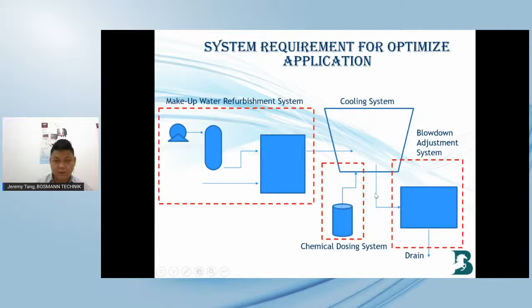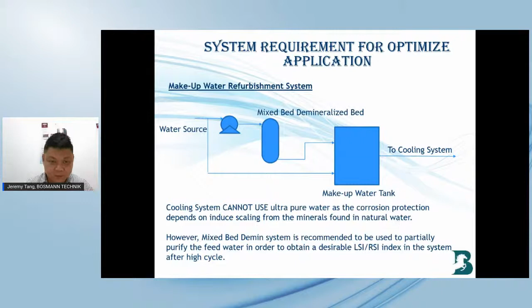Okay, a cooling tower cannot use wholly pure water, the so-called DI water, because corrosion protection depends on the induced scaling from the minerals found in natural water. So the DI system has to mix with the water source, the so-called government water, so it can run the cooling water system at high cycle.